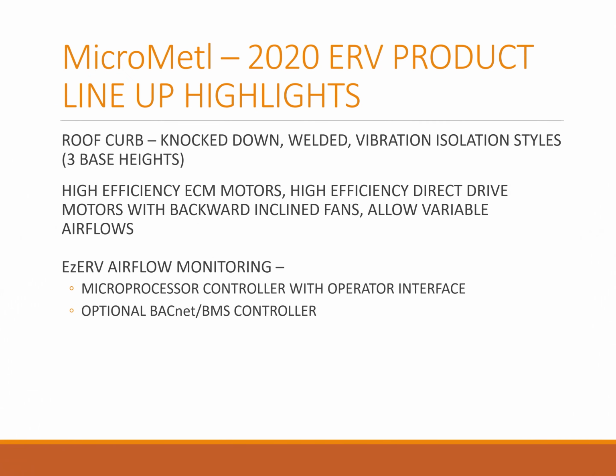Other related ERV products and options include roof curbs, including knockdown, welded, or vibration isolation styles in 3 base heights, high-efficiency ECM motors, which have backward inclined fans and allow for variable airflows, and EzERV airflow monitoring featuring a microprocessor controller and an operator interface. This controller also has options for BACnet or building management systems.